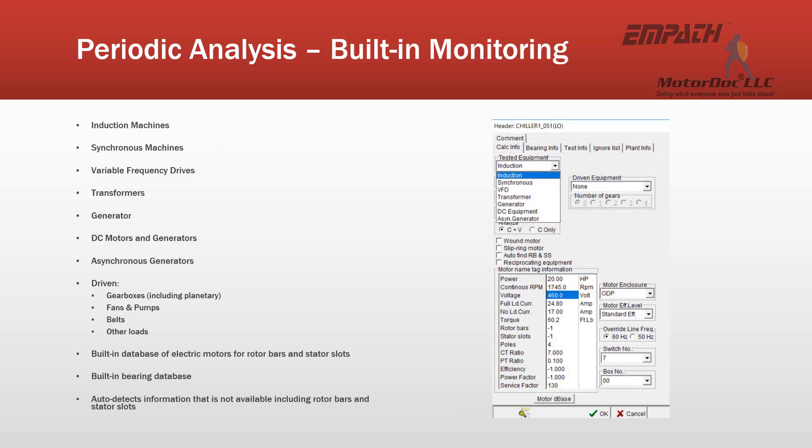It does a periodic analysis with built-in monitoring for induction motors, synchronous machines, variable frequency drives, transformers, generators, DC motors and generators, asynchronous generators, as well as driven equipment including gearboxes, planetary gears, fans, pumps, belts, and other loads. It has a built-in database of electric motors for rotor bars and stator slots, and a built-in bearing database so that you don't have to go look for that information ahead of time. It also auto-detects information including rotor bars and stator slots, as well as identifying potential bearing problems if the bearings aren't entered.